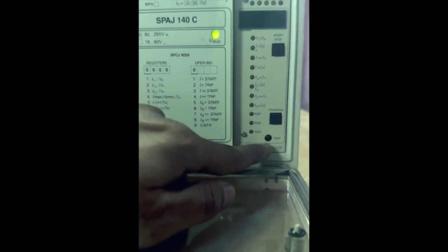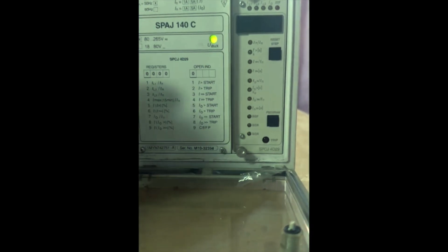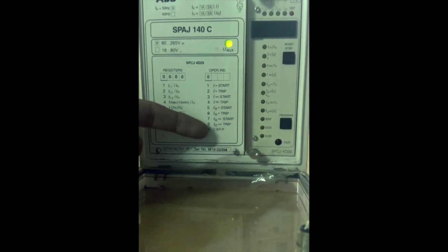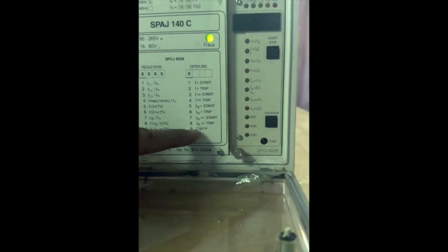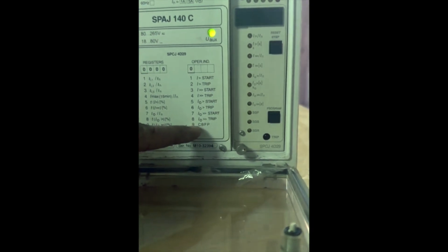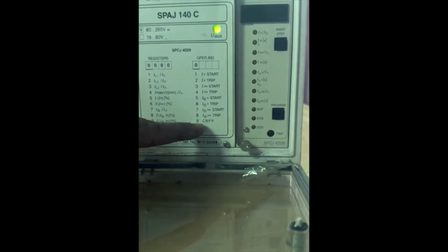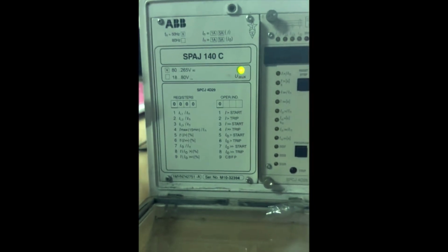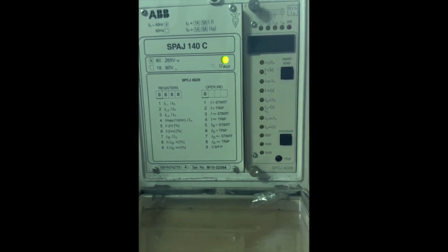Whenever a relay trips, it will display a trip indication here. You need to check that. Whenever a relay trips out, you need to see what's mentioned there. If the number 9 appears, you need to check if your breaker is experiencing a delay. There's a breaker issue causing the breaker to trip with a delay. The relay is tripping perfectly, but the breaker itself is slow to operate. We call it LBB or CB fail. So the relay guides you in that.